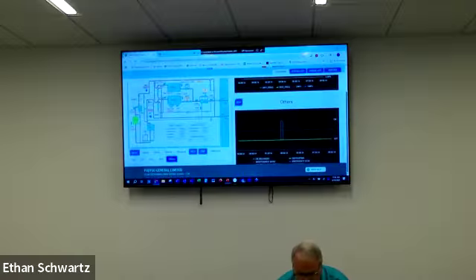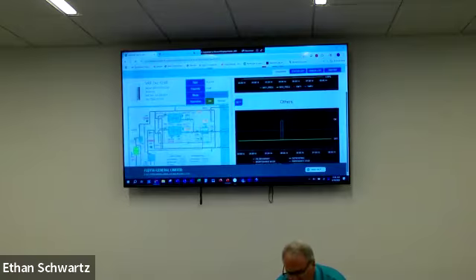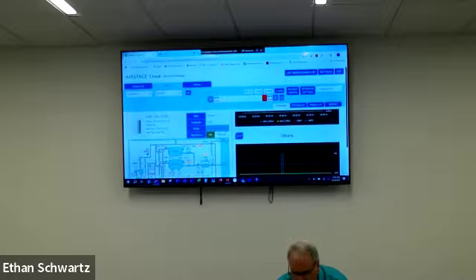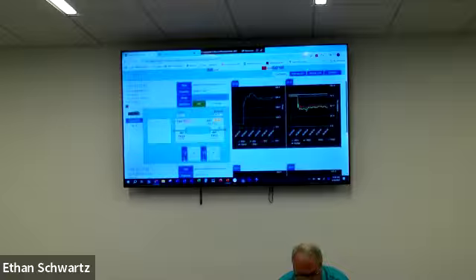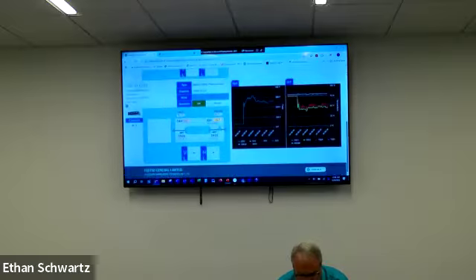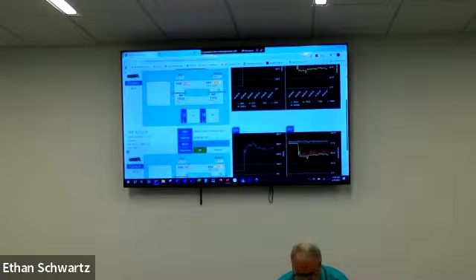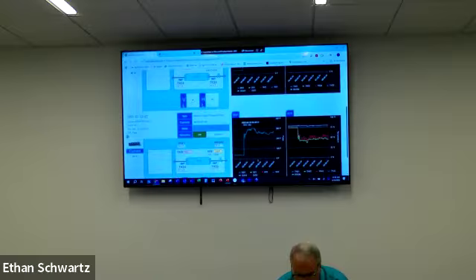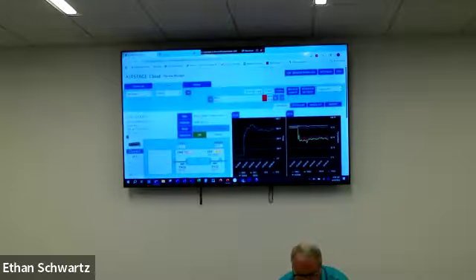So this is giving you an idea of the depth of information that a building owner would get. But not just that, because that's more important, particularly if it has maintenance staff or the contractor has a maintenance agreement with them. But we would be able to control and adjust all of the equipment. We can see here, these units are in cooling. And this is the EEV pulse rate. This particular system I'm working on, because they don't have sufficient airflow across our equipment, we're getting these kind of squiggly lines. So it's hunting a little bit to find an operational set point.